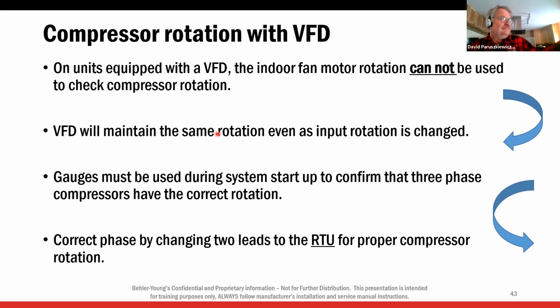I know it's 12 degrees right now with 2.5 feet of snow, and you're starting a rooftop unit today, and you don't really want to turn the compressors on. Well, the only way to check compressor rotation is by turning them on. Put a gauge on them, check rotation. Your suction pressure should fall, head pressure should climb, and they shouldn't make a lot of noise. But it's the only way you can do it.